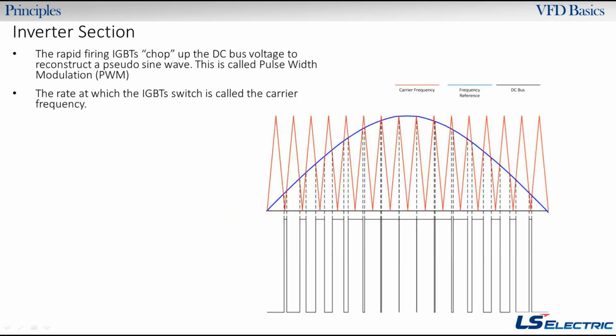So here's kind of what the output of the drive looks like. These rapid firing IGBTs, which are just transistors, are taking DC bus voltage, chopping it up, and reconstructing a pseudo sine wave. It's not going to be exactly a sine wave, but it's going to be something close. The waveform that we're outputting is actually a PWM waveform, which is a pulse width modulated waveform. You may have also heard the term carrier frequency. Carrier frequency is the rate at which we're turning these IGBTs on and off.